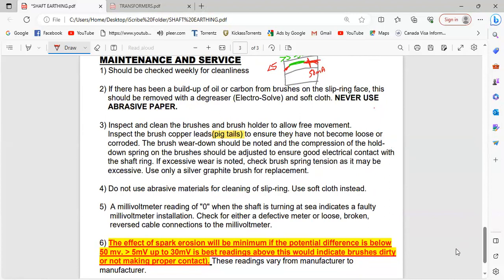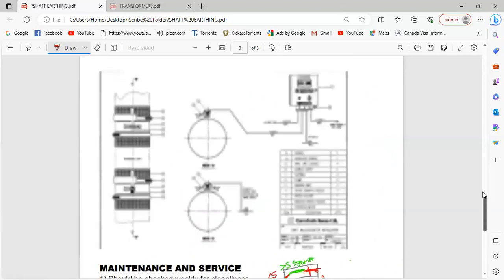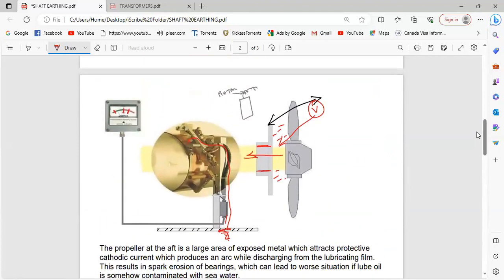If the millivolt meter is reading zero when the shaft is turning out at sea, it indicates a faulty millivolt meter, or there might be a break in the line. Okay, so going back to this particular thing, either this one has gone kaput, or the connection between here and here has gone kaput, or your particular earthing here for this meter is not making properly. Okay, so check the other way around. Don't directly assume your meter is faulty. Check all the connections. Maybe the earthing connection inside has slipped out or something like that. Okay, lastly, you will be able to come to the conclusion that your meter has gone kaput.